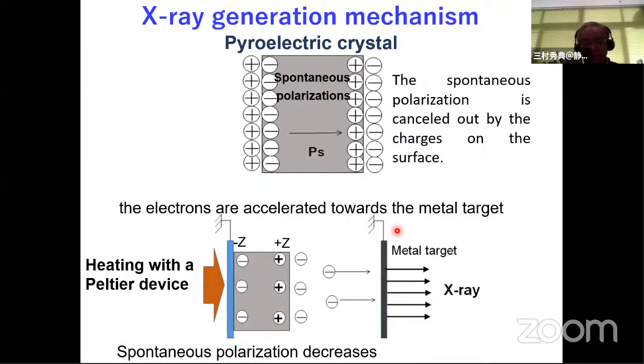This slide shows the X-ray generation mechanism in the Cool-X. In a pyroelectric crystal, spontaneous polarization is generated like this. This spontaneous polarization is cancelled out by the charges on the surface at room temperature. The temperature is increased by heating with the Peltier device. The spontaneous polarization decreases, and the surface potential becomes negative. The electrons are emitted from the top of the surface of the crystal and accelerated towards the metal target, and the X-ray is generated.